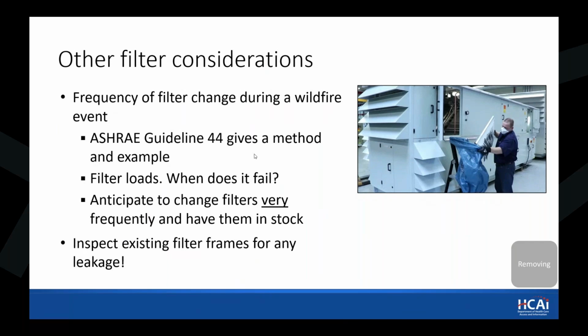There is an example in Guideline 44, and the calculation method, for you to estimate how frequently you need to change your filter during the wildfire smoke event. Irrespective of whether you do the calculation or not, expect that you're going to change your filter very, very frequently. Depending on your proximity to the fire and the wind direction, I've seen facilities having to change them as soon as 2 to 3 days. So you're talking about days versus the normal schedule, which is 3 to 6 months.